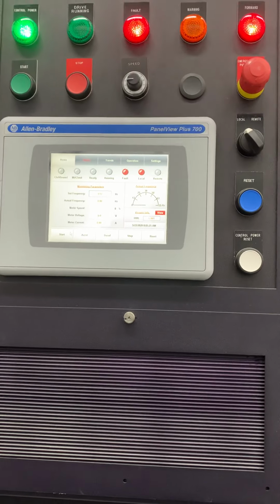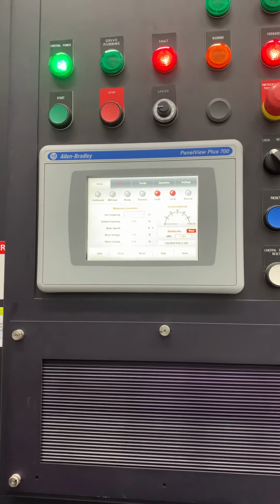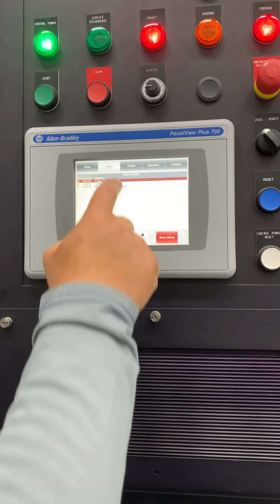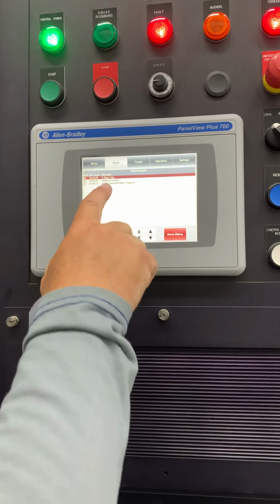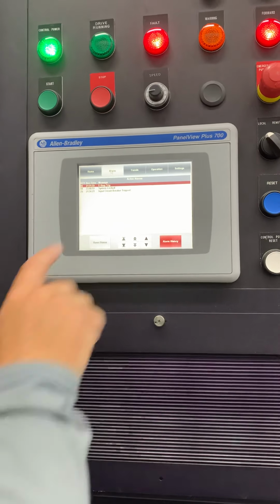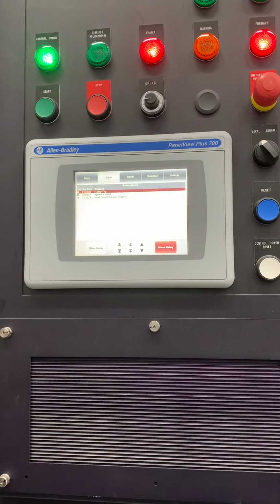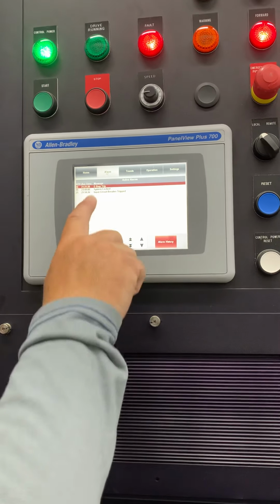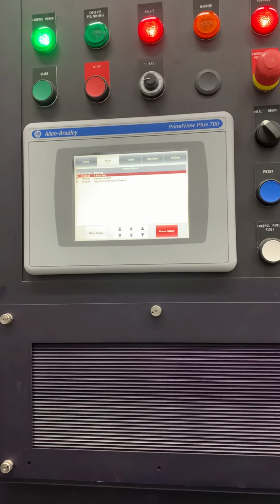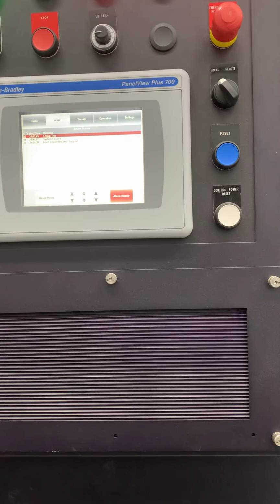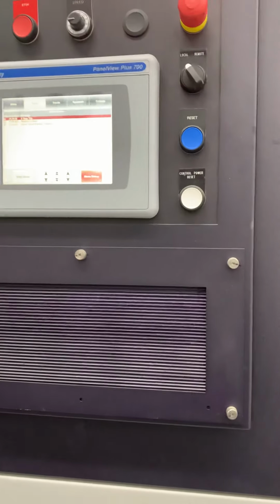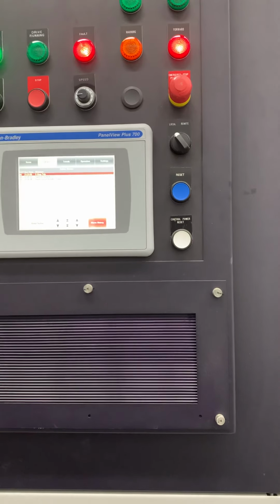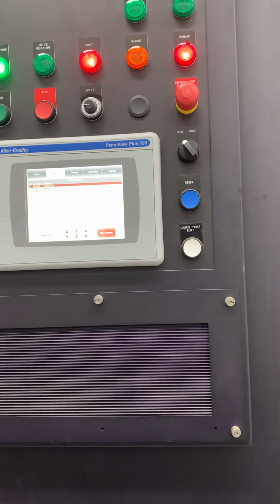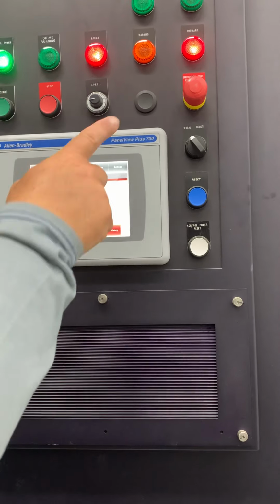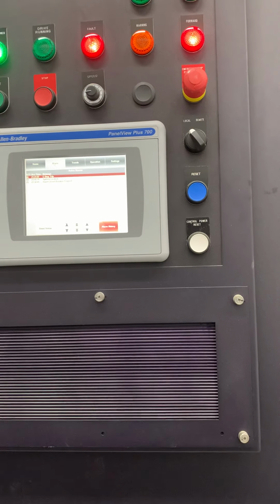And then if you have alarms, so if you have a fault or whatever and you want to know what it is, just tap on the alarm screen and it'll tell you the e-stop is tripped because the e-stop's in. System's locked out because the e-stop's pressed and there's no power to it. The input circuit breaker is tripped, because it opened up the contactor when you hit the e-stop. So those three errors are very common. That just means you need to pull the e-stop. So if you had other e-stops on the system, you'd need to pull those out. Make sure they're all pulled out and then do a reset, and those will go away.